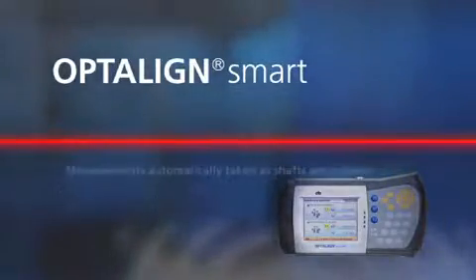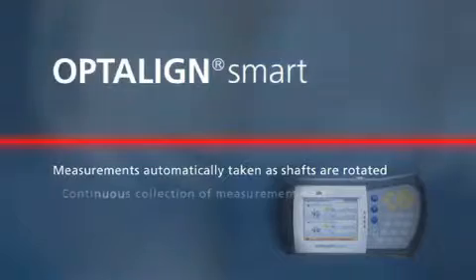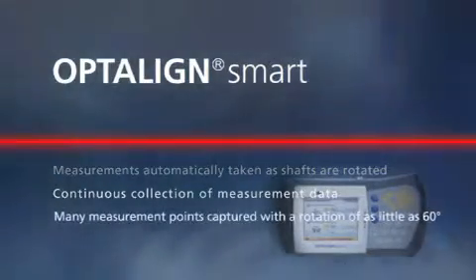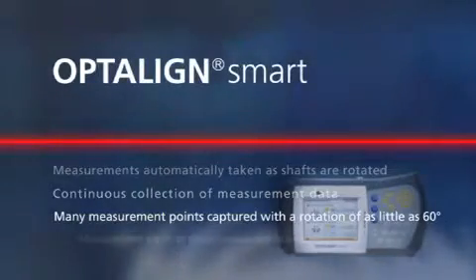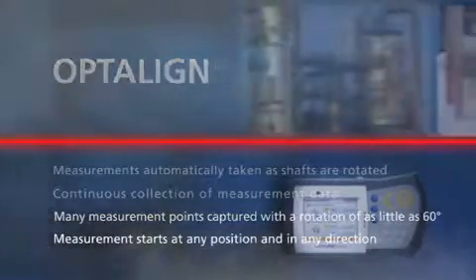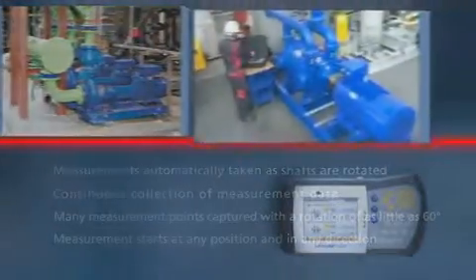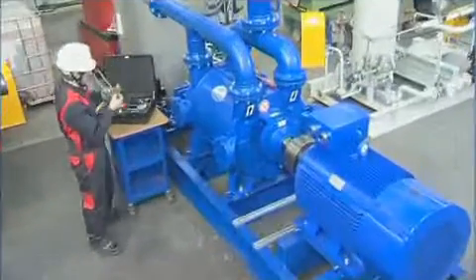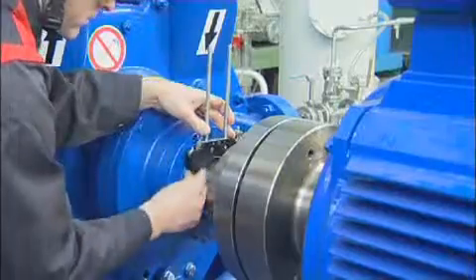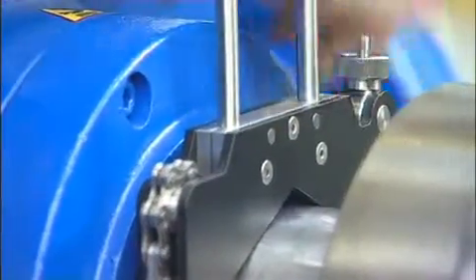OPTALIGN smart automatically takes measurements as shafts are rotated. It collects and computes data continuously. A shaft rotation of 60 degrees captures a large number of measurement points. Measurement can start in any position and the shaft can be rotated in any direction. OPTALIGN smart features fast and rigid mounting of the transducer and reflector on the shafts using pre-assembled brackets, which are designed for quick and stable mounting and setup.